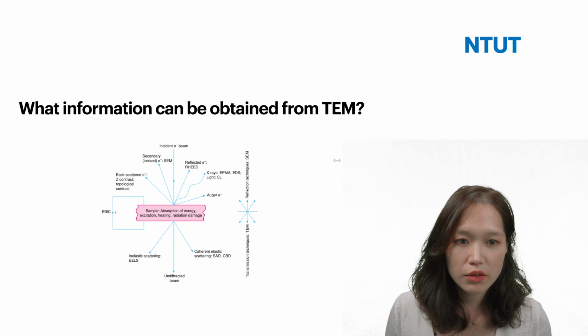For these sorts of TEM probes, it can go up to 1,000 degrees Celsius. But please remember when you're using this heating probe, what is your material? Can your material go up to this temperature?